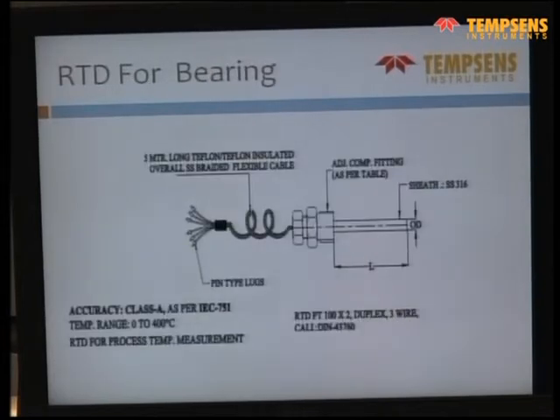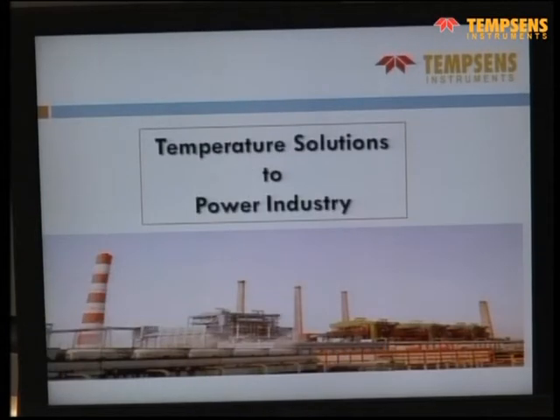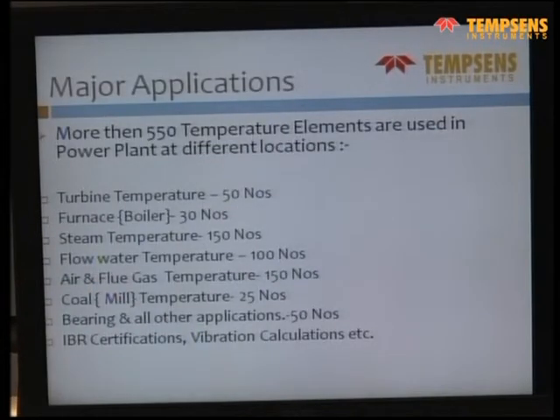For this bearing RTD, the diameter is small, but the problem is vibration and other things. So you need to take care at the joining of the RTD and the outer wire, and secondly of the RTD element itself, so that even in high vibration it gives a good life. For power plants, there are many solutions we are offering. Turbine temperature measurement, furnace boiler temperature measurement, which can be thermowells, and air and flue gas temperature measurement, coal mill temperature measurement, which is like tungsten carbide thermowells, bearing and IBR certification.